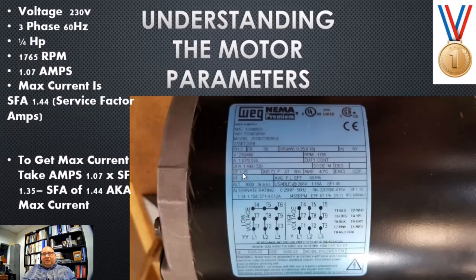You're left with a higher amperage than your running load amp. You have what's known as a service factor amp. Let's just recap this again. Your normal amps would be 1.07. Now when you times it by your service factor amps, you're left at 1.44. So your maximum current for this motor, when you program it in the drive, has to be set up for this amperage here, including your service factor. So the normal maximum will be 1.44. Anytime it would go over that, then the drive would either try to protect it on a safety, or if it continues to rise above that, it'll trip on a fault and try to protect itself.